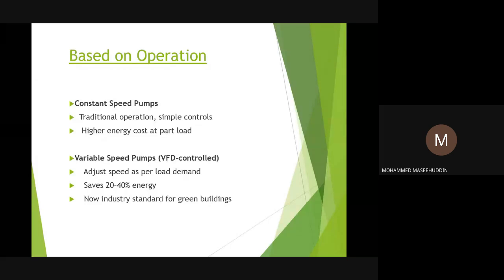Whereas in the secondary, since it is going up to the last point in the building, the last FCU, and when we are calculating the head also, we go up to the last FCU, the longest route, and then the water comes back to the pump again. So in that case, since these are varied loads, variable speed pumps are used mostly in the secondary chill water circuit. And now with the variable speed pumps, you can regulate the speeds from, let's say, 20%, which is 20 hertz, or even 10 hertz, up to 50 hertz. Since the VFD runs on frequency, which is 50 hertz in this part of the world, 50 hertz is considered basically as full load, which is 100%.